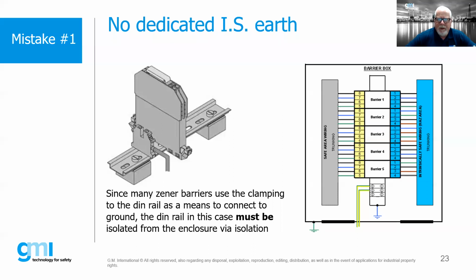There are a lot of issues with this IS earth, and if you see this slide, it's important to note that a lot of times the Zener barriers use the DIN rail as a means to ground, and that is the clean earth. So if we are using that DIN rail and attaching it to a metallic enclosure, then we're tying it all into the metallic enclosure. At that point, we want to make sure we're using isolated, insulated standoffs between the DIN rail and the metallic enclosure, so that we're not tying it into the dirty earth.